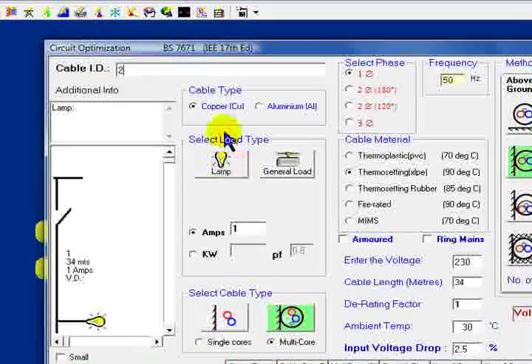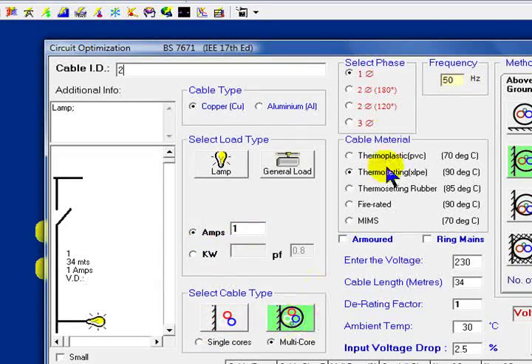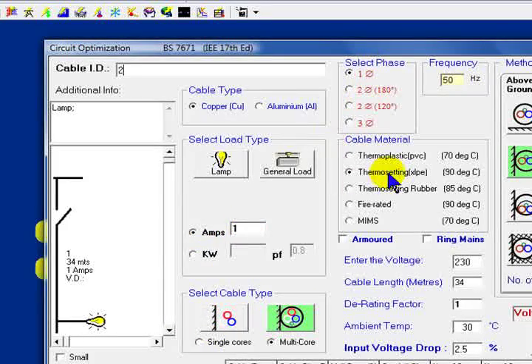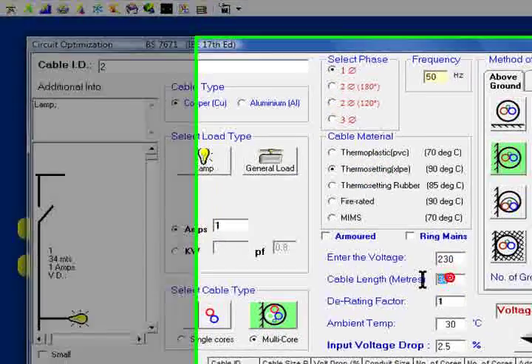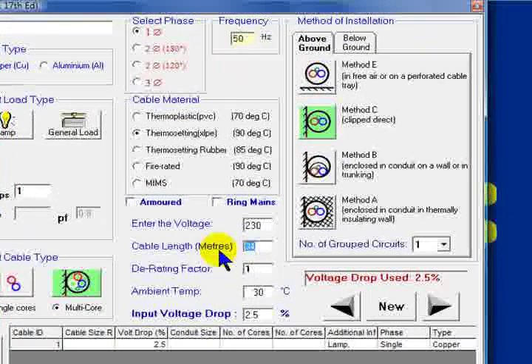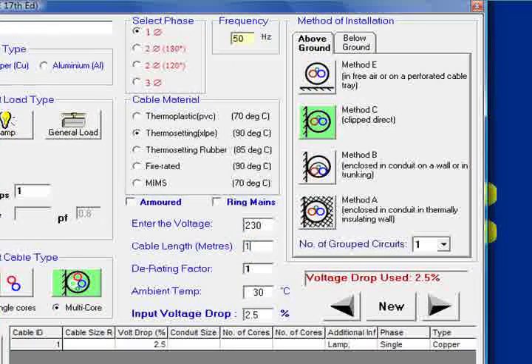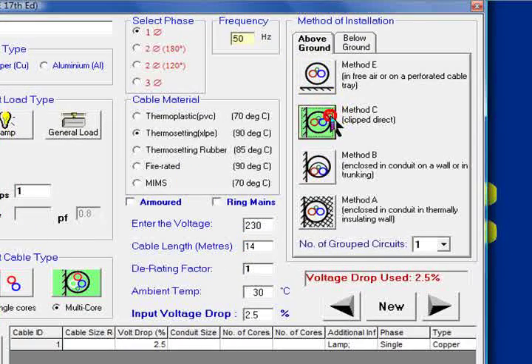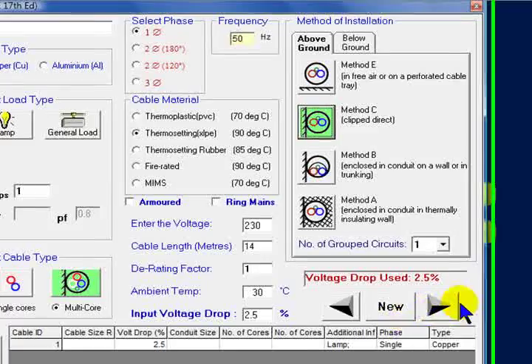Cable number 2. Same again, it's a lamp, 1A load, multicore, single phase, 90 degrees C. Length of the run this time, we'll make that 14 meters. Have it clipped direct, and on to our next cable.